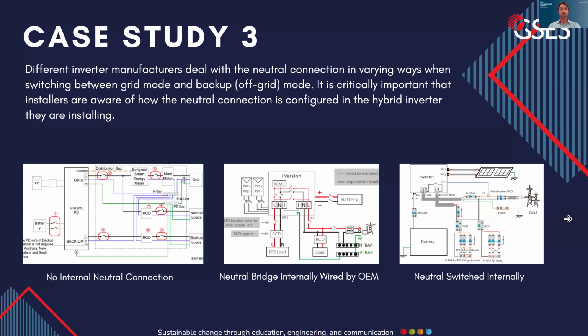This often requires external neutral bridging to be made by the installer, and you should be checking with the OEM installation guides. Each of these configurations affects how you should approach installation, as well as testing and commissioning. Always check the specific inverter's manual and manufacturer guidance to avoid errors and ensure neutral continuity in various modes, and especially during your commissioning and testing.